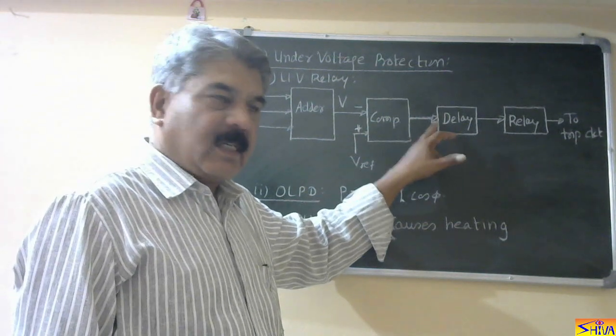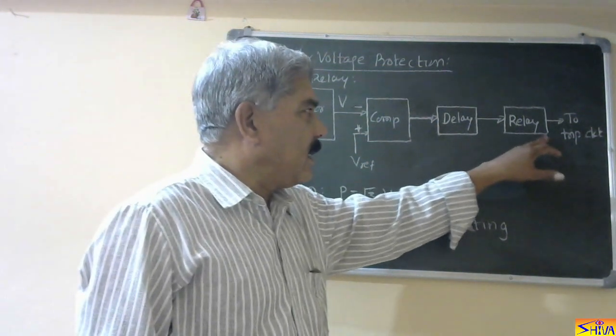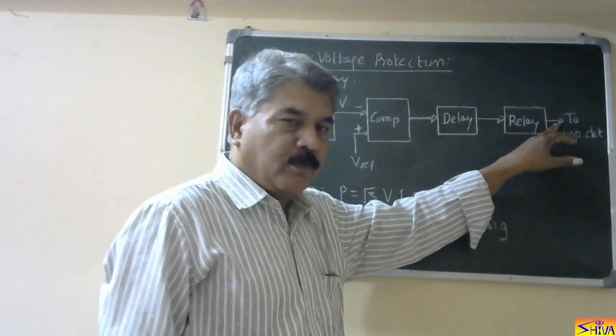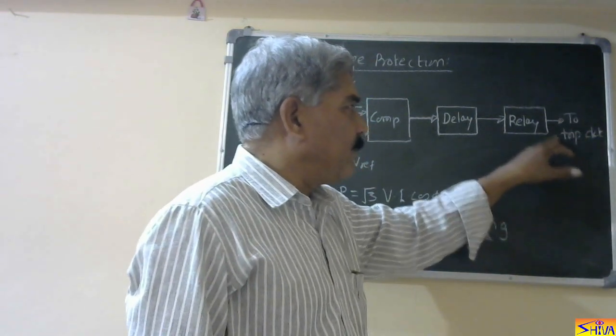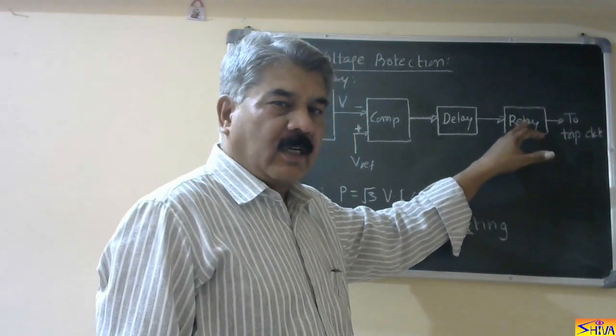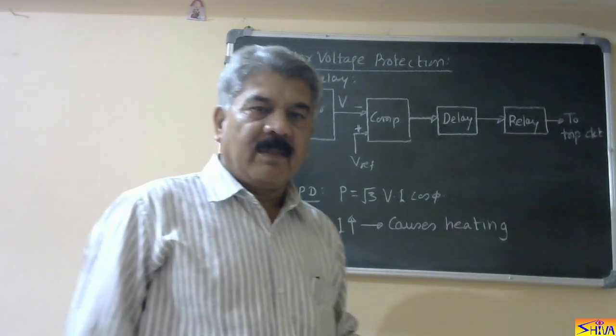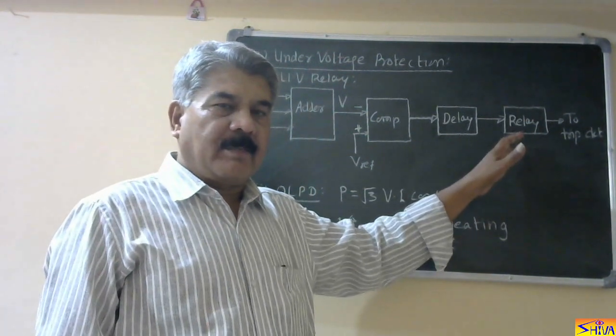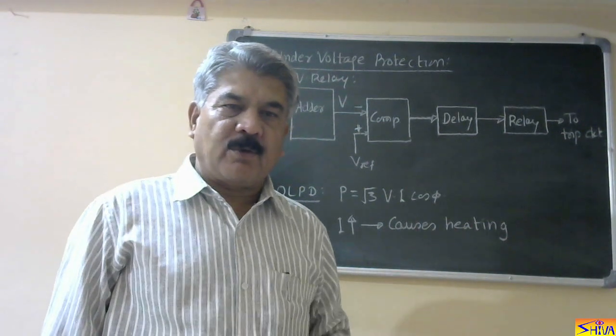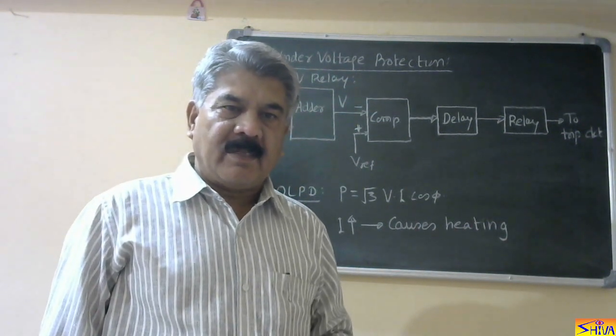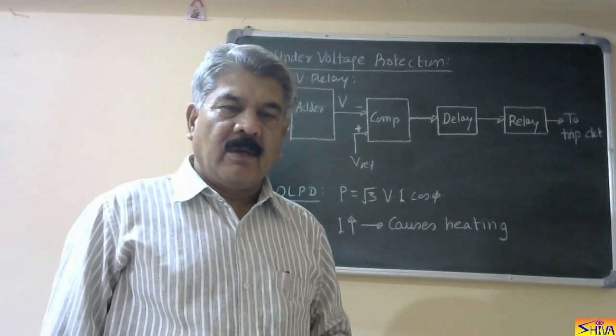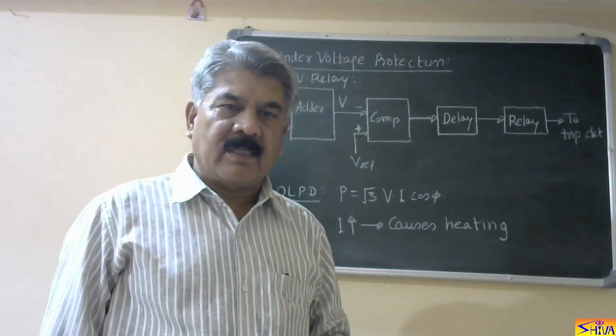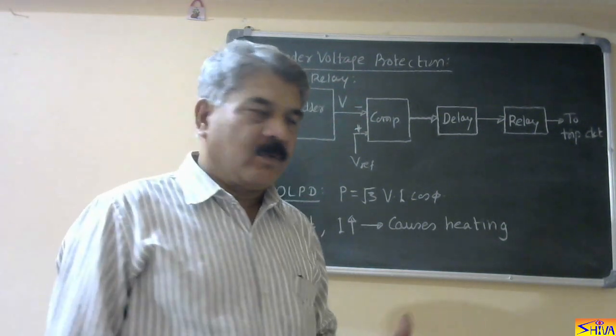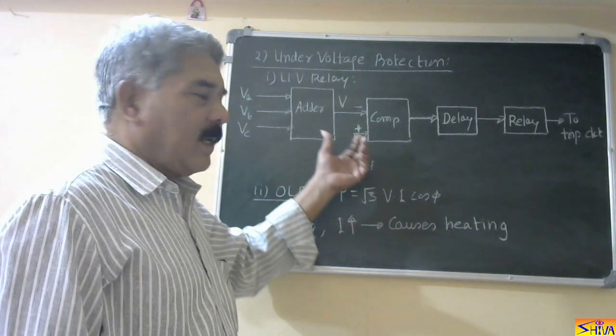If the condition still persists, then this relay trips and the relay output becomes high, and this is going to the trip circuit. Normally, the close contact of this relay is connected in the trip circuit, and when this contact becomes high, whatever is the protective device, that is MCB, MCCB, thermal overload relay or differential relay or instantaneous relay, that will trip. So this is how the under voltage relay works.